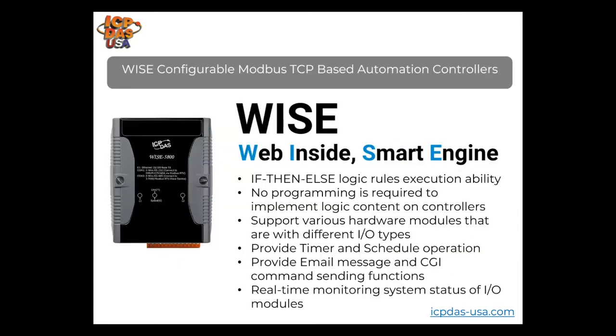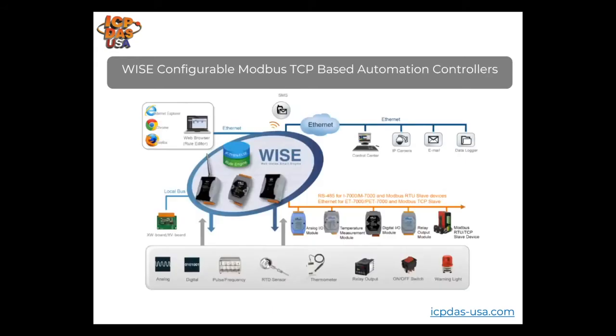Our WISE data acquisition modules are intelligent I/O modules that have special firmware. It allows them to implement control logic and other functions through configuration through a web page. They're used for monitoring and control, and they can send email alarms out based on conditions, like when a digital input turns on or when an analog input reaches a certain level, so personnel can service equipment or proceed with processes. Our WISE 7000 series are data acquisition modules that have control capabilities.